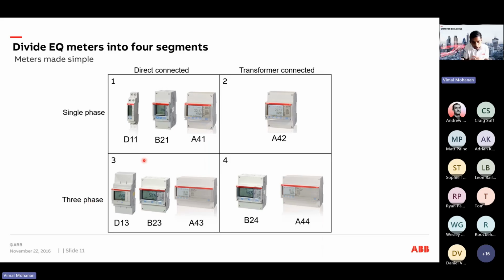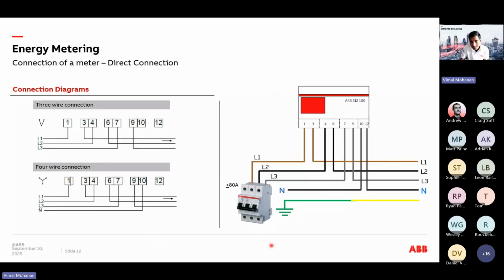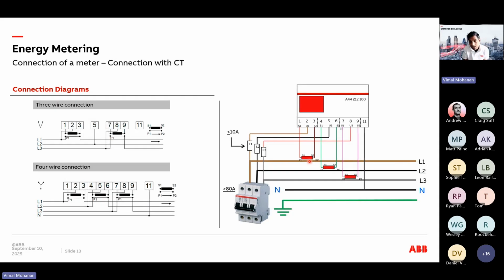For people who haven't used metering or aren't sure what direct connected and transformer connected mean: if the incoming supply, say in your own house, is a 63 amp or 100 amp incoming, meters can take that current directly into them. In the ABB world, up to 80 amps we can take directly into and out of the meter. But for bigger properties, big multi-million pound houses, potentially with a three-phase 125 or 150 amp incoming, that current cannot be connected directly to the meter, and you'd require CTs, or current transformers.